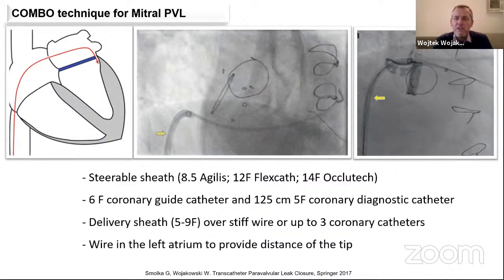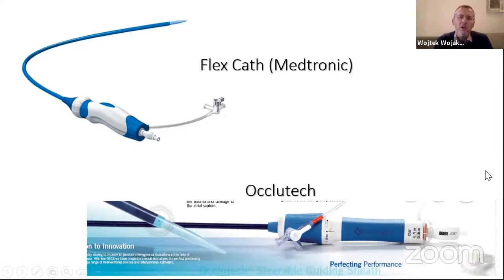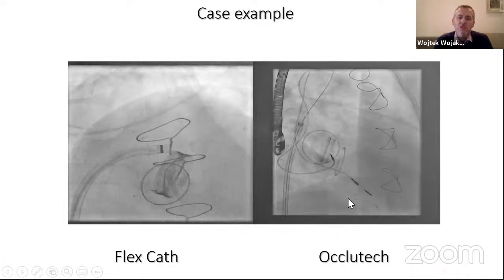And then you can use either single or triple delivery sheaths when you use the large size catheter. So the one from Medtronic we use is the one that's usually used by electrophysiologists for the cryoablation. In Europe, there is an Occlutech sheath, a 14 French sheath, which is deflectable, as you see, and it's really easy to use for the PVL closure. So this is an example of the FlexCath with the diagnostic catheter inside and the Occlutech sheath.